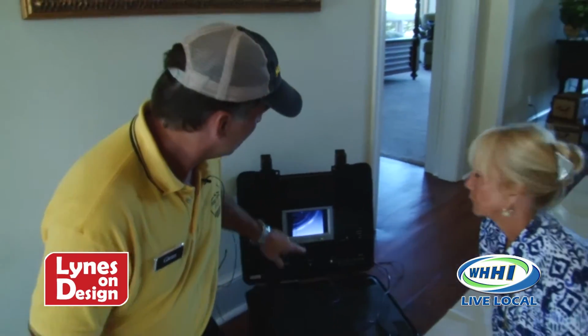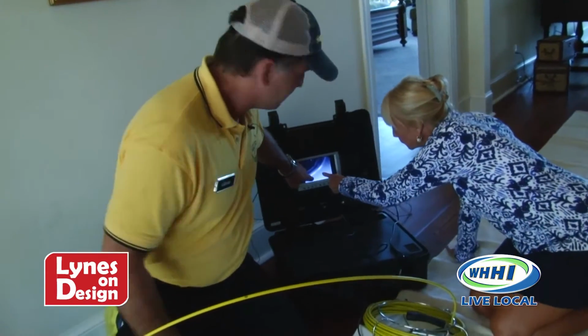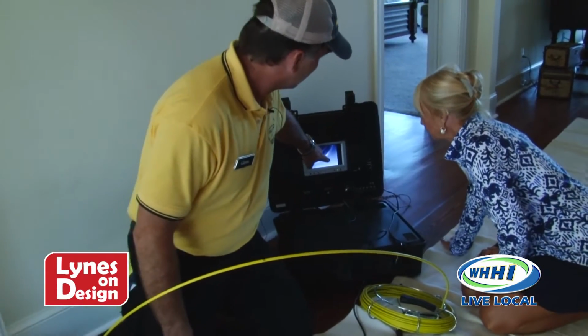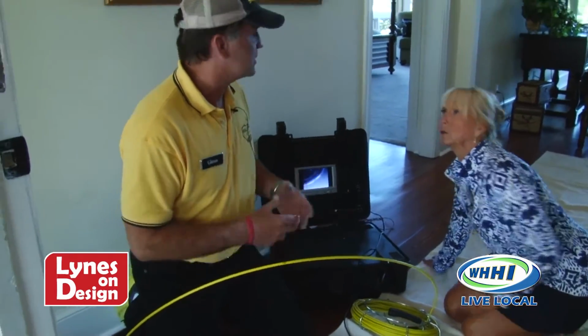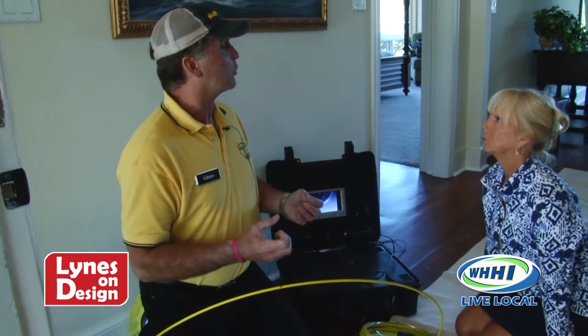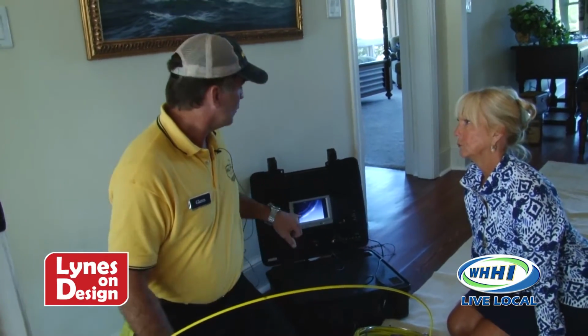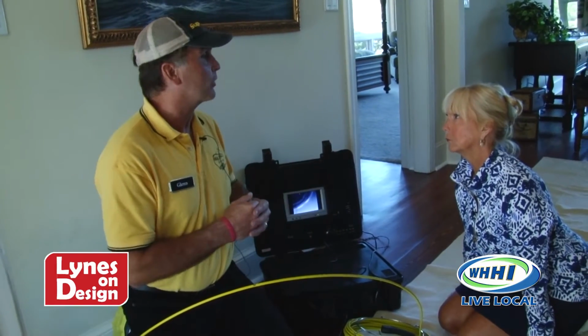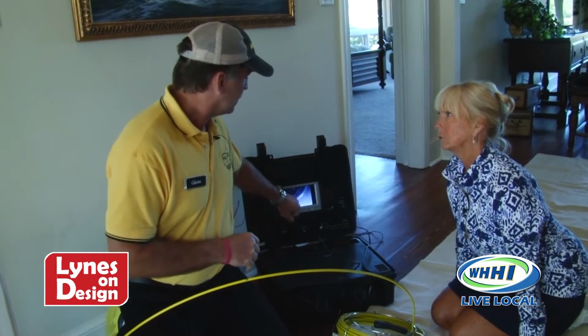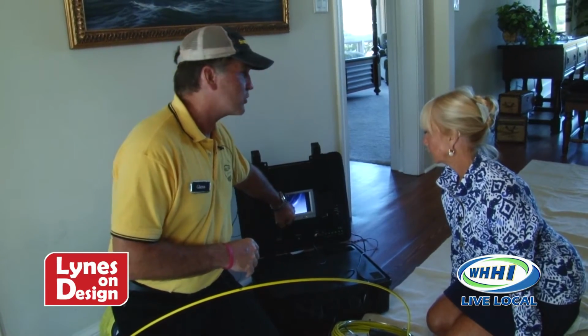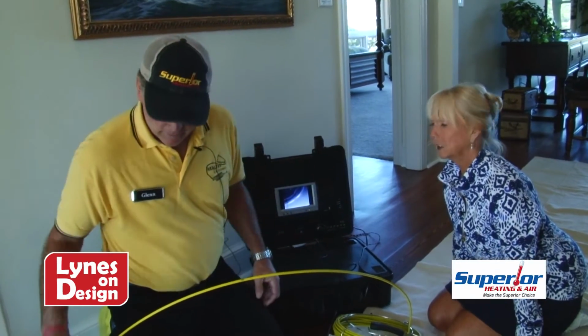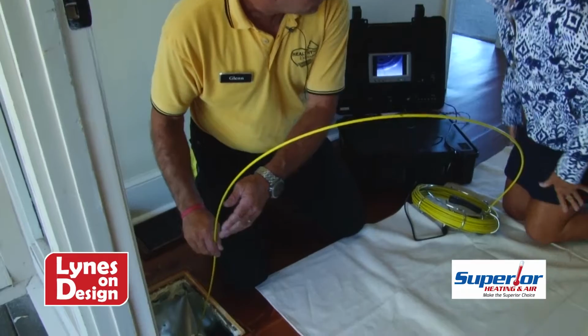After the homeowner installed it, they had some construction work done, and you can see this white pigment here—that's actually drywall dust. Drywall dust is a moisture-absorbing material, so when you get condensation in your pipes, which you normally would because of the heat difference in the attic we talked about earlier, it becomes a food source for bacteria or mold. So you want to get the dust out.